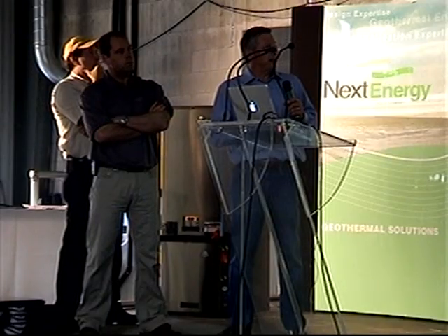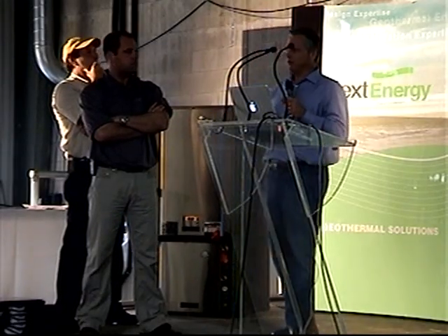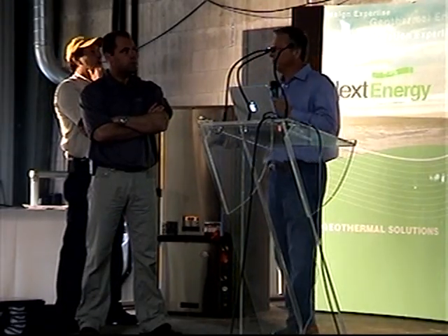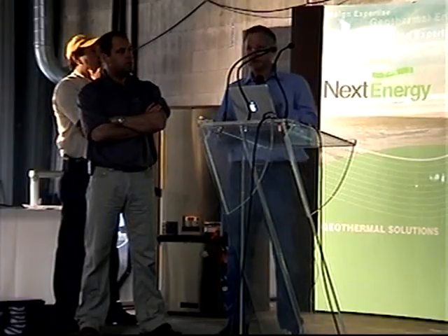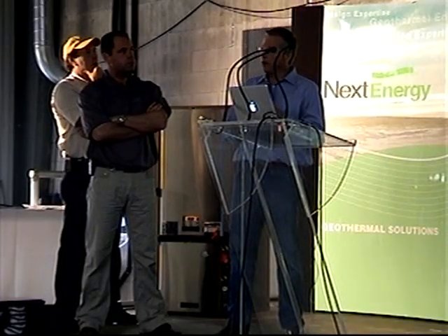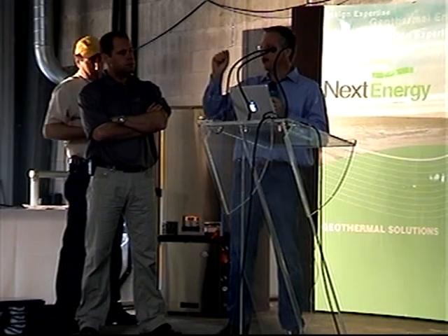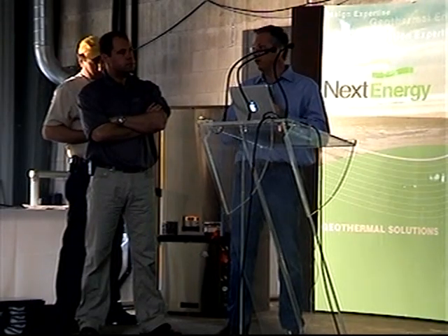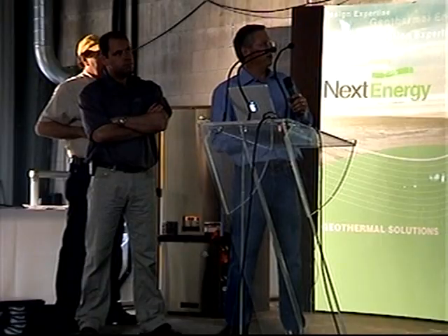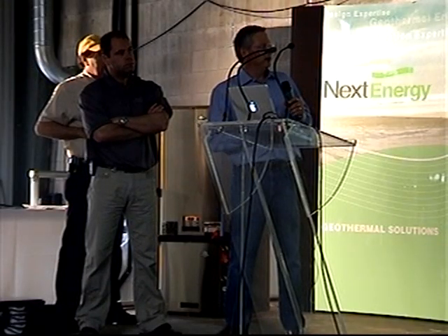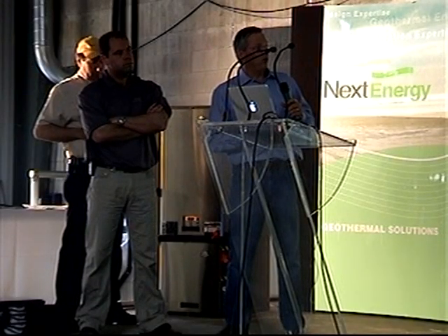Let's see, a diagnostic LED on the board. People have said, geez, why not have it on the front of the unit? Well, the reason we don't is because a lot of times the units are not that convenient, and we have a way in our board that you can see at the thermostat the reason for the fault, which hopefully will be in this slideshow here in a minute. Yeah, fault readout at control board or the thermostat.